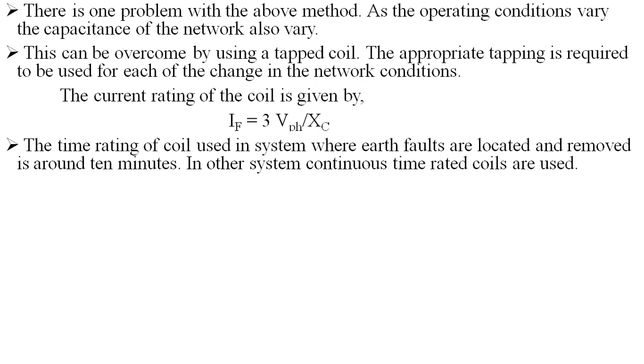So in the other system, continuous time rated coils are used. The coil is tapped in order to select the reactance depending upon the length of the transmission line and the capacitance to be neutralized. The arc suppression coil is connected between the neutral and ground. The reactance of the coil can be evaluated by using the expression L = 1/(3ω²C). So the rating of the coil is continuous and equal to the maximum earth fault current.